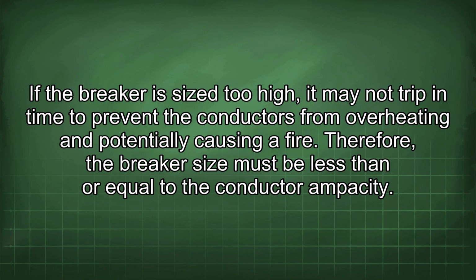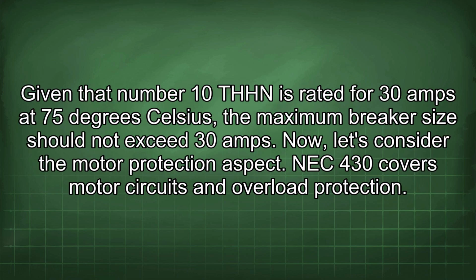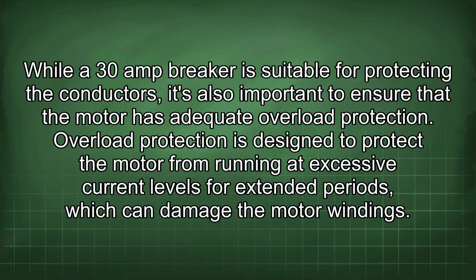Therefore, the breaker size must be less than or equal to the conductor ampacity. Given that number 10 THHN is rated for 30 amps at 75 degrees Celsius, the maximum breaker size should not exceed 30 amps. Now let's consider the motor protection aspect. NEC 430 covers motor circuits and overload protection. While a 30 amp breaker is suitable for protecting the conductors, it's also important to ensure that the motor has adequate overload protection. Overload protection is designed to protect the motor from running at excessive current levels for extended periods, which can damage the motor windings.